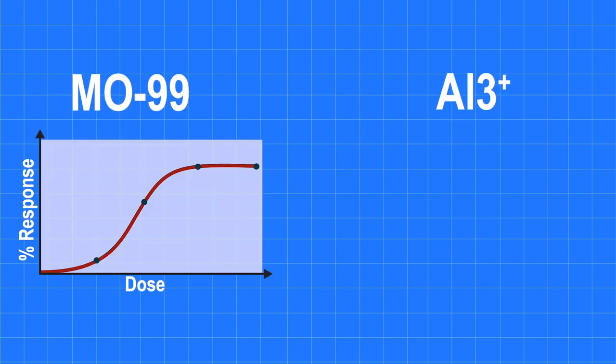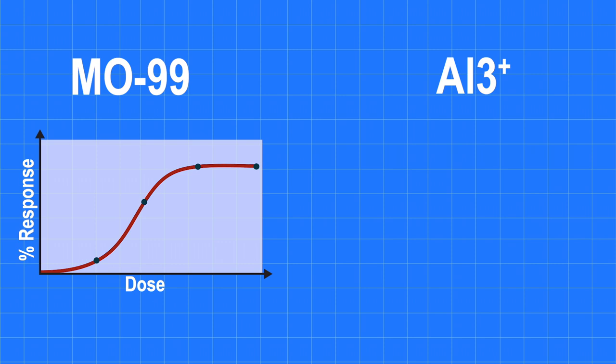Two impurities may be present in the eluted solution, molybdenum and aluminum ions. Excess molybdenum will increase the patient dose without providing benefit. Quality control tests are performed to rule out the presence of these contaminants.